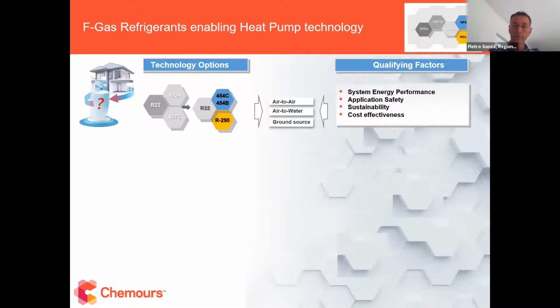The industry, from an historical perspective, has seen a multi-decade convergence towards a narrow range of refrigerant fluids. Like many other applications based on vapor compression, this technology developed around refrigerants like R22 and hydrochlorofluorocarbon, and then evolved adapting to hydrofluorocarbons, HFC solutions, mainly R410A, estimated at covering about 75% of the installed fleet, and R407C or R134A estimated to jointly cover the remaining quarter of the total market from a European perspective.